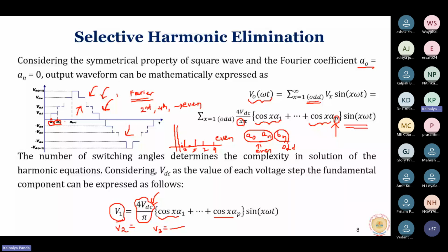So now we are trying to focus on the odd order harmonics only. And from this odd order harmonics, if you see the harmonic profile, if you go to the 49th order, let's say, you will see at higher order the magnitude of the harmonics is very, very low. Whereas at the lower order harmonics, like third, fifth, seventh, ninth, the magnitude is very, very high. So our focus should be on these orders.